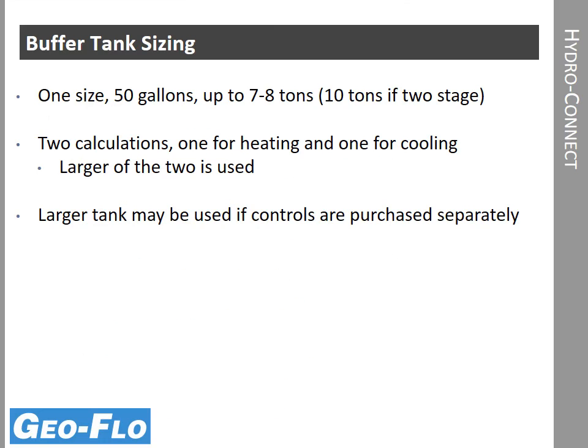The next webinar actually goes into detail on buffer tank sizing. So the size that's available currently is one size. It's 50 gallons, and the reason 50 gallons was picked is because that is typical for 7 to 8 tons if the water-to-water heat pump is a single-speed machine, or if it's a 10-ton unit and it has 2 compressors or 2 stages, then the buffer tank is still 50 gallons is still appropriate.